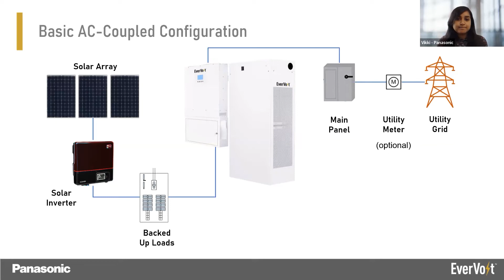If the customer wants more backup power, there are multiple options, including an ATS, for achieving whole home backup configuration. I say whole home backup configuration because it's not always 100% whole home backup itself. That's something to be mindful of when quoting a customer and planning the system design. We can stack multiple systems and have an ATS for switching over during the outage to achieve whole home backup.